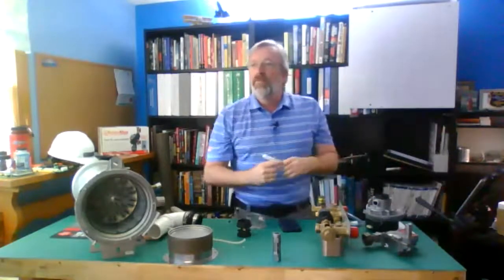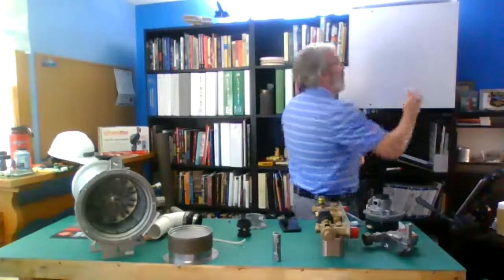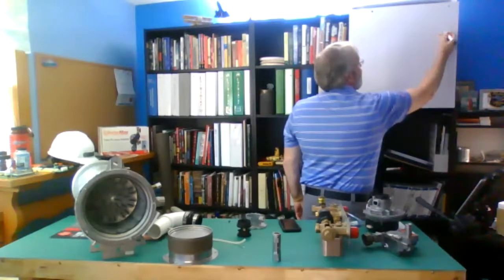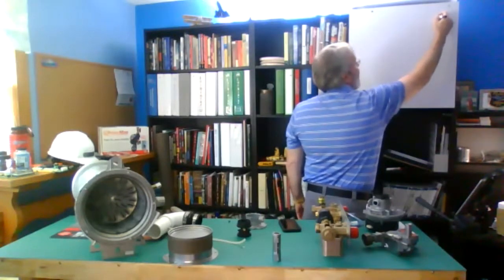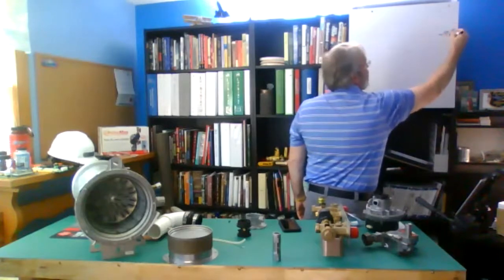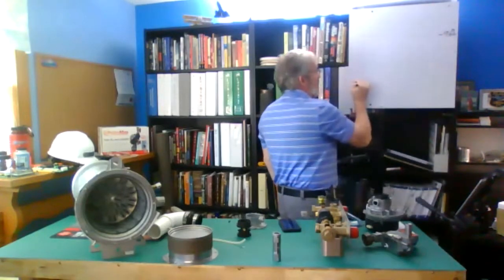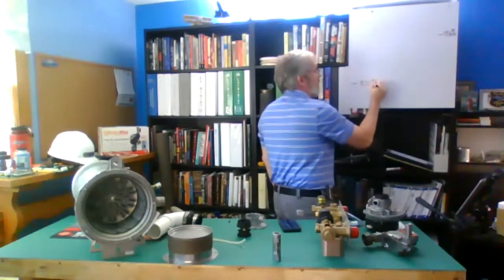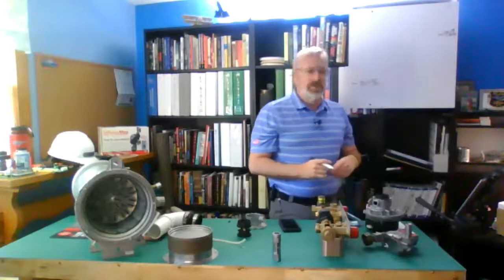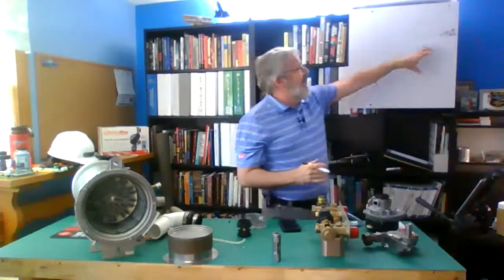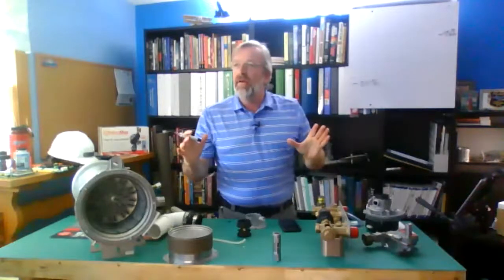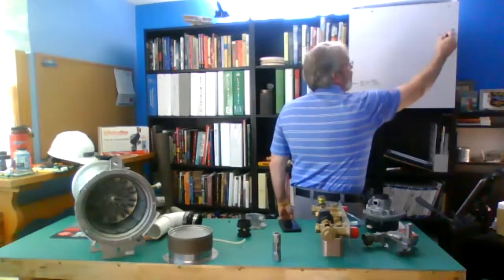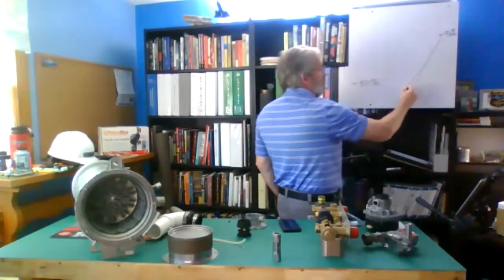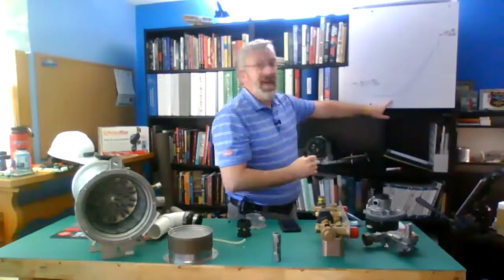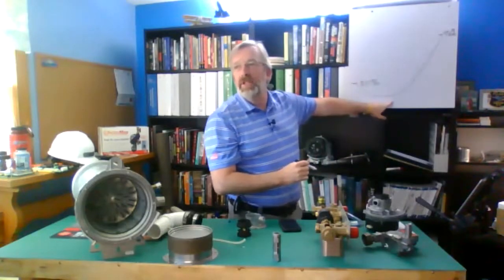And so it really gets into how the boiler is going to adjust in that ramp from high to low fire. So if I've got a scenario where my high fire is here, and we're just saying this is in my range, and we're calling that the 9.6%. But my low fire is here. You guys see that? 8%, 9.6% is what I've got there. And even though those numbers are okay, when my boiler adjusts, I get a droop. And that droop can look something like this. And that spot in the middle is out of range.